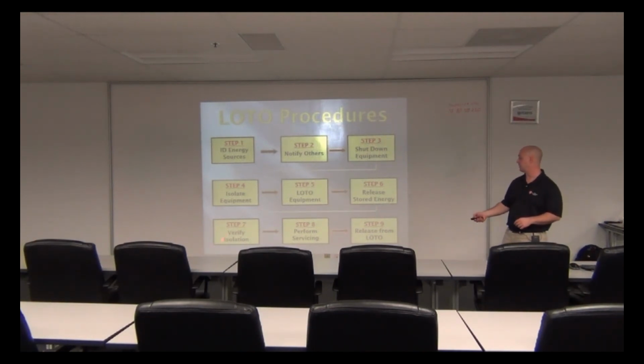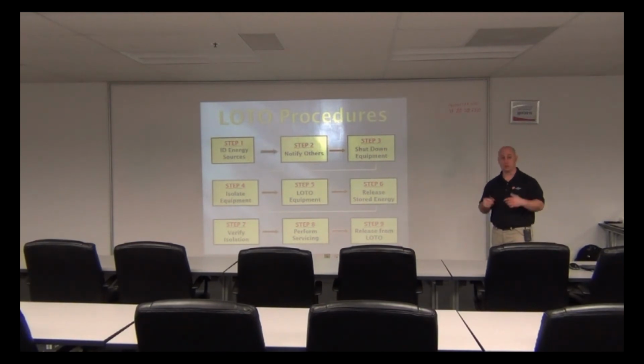Then you're going to verify isolation - one of the ways is you may test with a multimeter. So if you're on the switch on the wall, you turn it off, but you have to do work on the plug at the bottom. When you get to the plug, you're going to test to make sure there's no voltage going to it. Once you know that, you can perform maintenance. But another way to verify is to simply try to turn on the piece of equipment - that's another part of that step. Turn it on, doesn't work, turn it back off. Do all the verification you need though, don't just simply turn it on and turn it off - that may not be all you need to do.